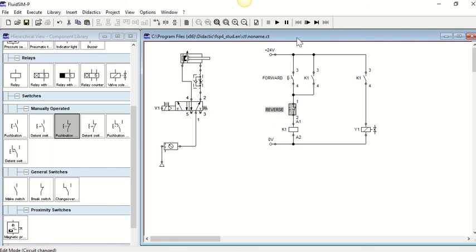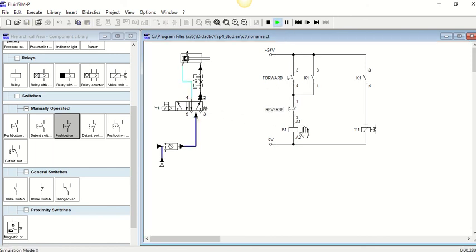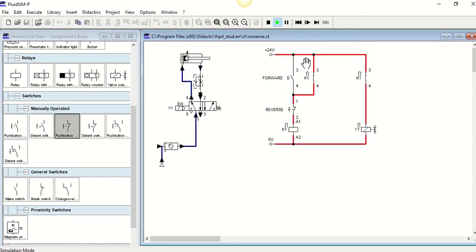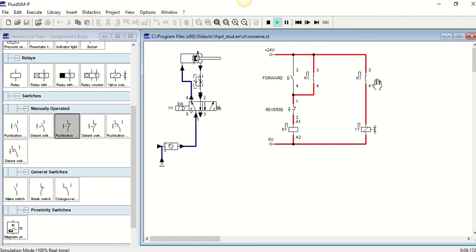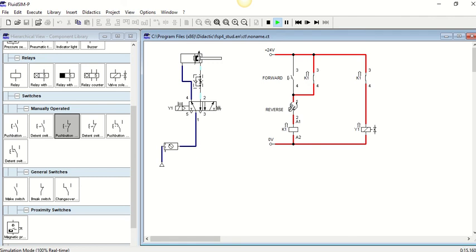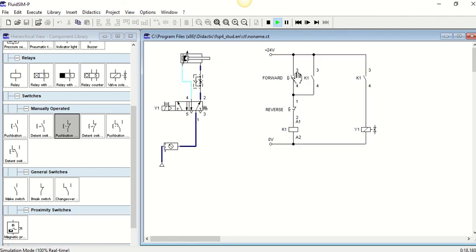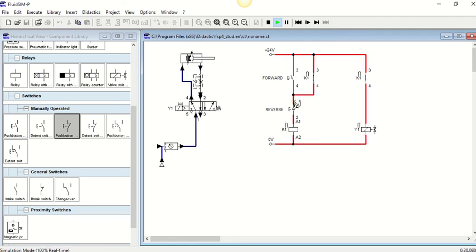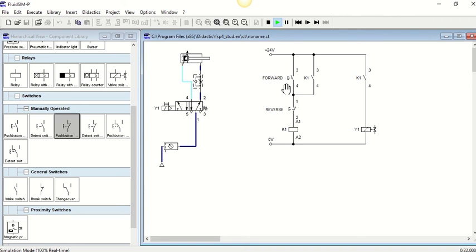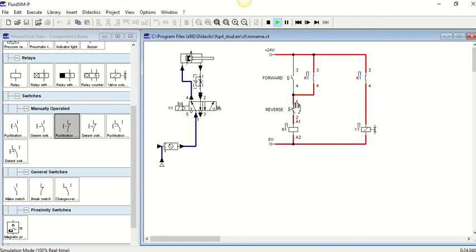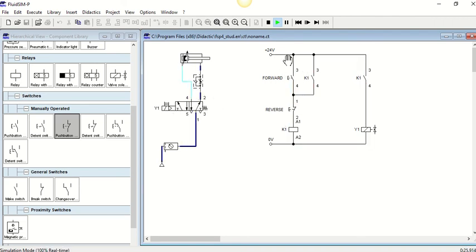They are going to do the exact same thing. So we have now incorporated a relay, this K1, which is going to latch itself on. See the way it is allowed to pass through that normally closed push button, keeps it powered up so that we don't have to keep our finger on the button. It moves the full way forward. And then we hit reverse when we want to bring it back. Even if we wanted to bring it back halfway, at the halfway mark, we can do that. We are breaking that latch.